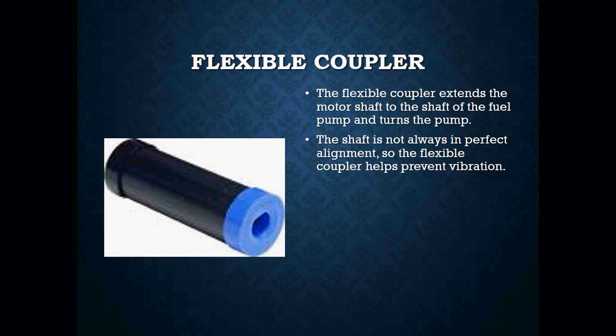Your flexible coupler extends the motor shaft to the shaft of the fuel pump and helps turn the pump. The shaft is not always in perfect alignment, so a flexible coupler helps prevent vibration. When working on burners, we want to inspect the coupler and make sure the ends are not damaged. If the ends are stripped out or broken, your blower, coupler, and fuel pump probably will not spin. You need the flexible coupler installed for the fuel pump to spin.